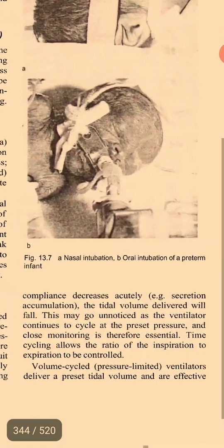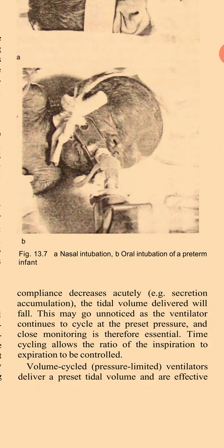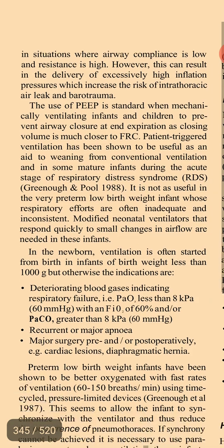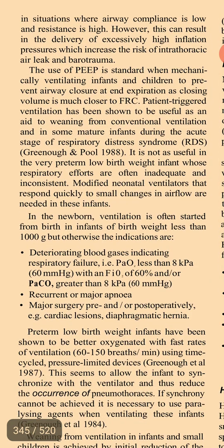Volume cycled, pressure limited ventilators deliver a preset tidal volume and are effective in situations where airway compliance is low and resistance is high. However, this can result in the delivery of excessively high inflation pressures which increase the risk of intrathoracic air leak and barotrauma. The use of PEEP is standard when mechanically ventilating infants and children to prevent airway closure at end expiration, as closing volume is much closer to FRC.